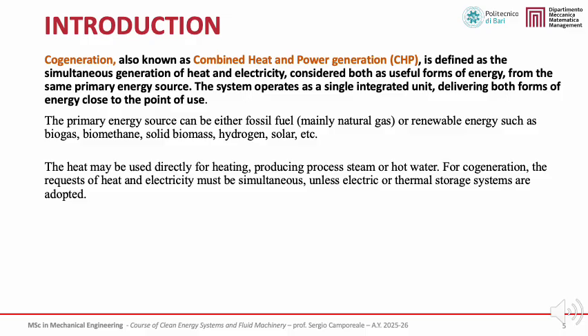The primary energy source can be fossil-based, most commonly natural gas, or renewable, such as biogas, biomethane, solid biomass, or hydrogen. The recovered heat can be used for space heating, hot water production, or industrial process heat, including steam generation. An important operational aspect of cogeneration systems is that the demands for heat and electricity must generally occur simultaneously. Only when thermal or electrical storage systems are introduced can this coupling be partially relaxed, allowing greater operational flexibility.